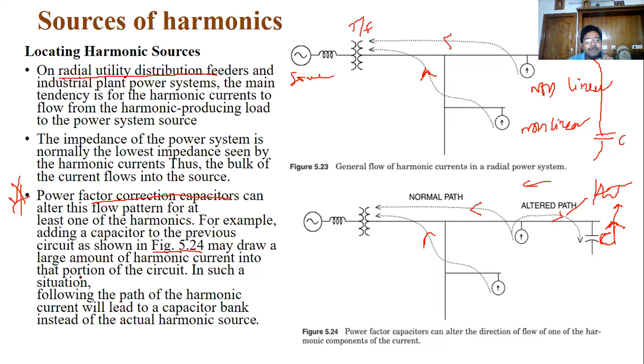Now see this. In this example, because of adding the capacitor to the circuit, it may draw a large amount of harmonic current into that portion of the circuit. So you can see the capacitor is drawing a large amount of harmonic current. The harmonic current is diverted to the capacitor. This will lead to the capacitor bank instead of the actual harmonic source. So now see, the capacitor is storing this harmonic current.